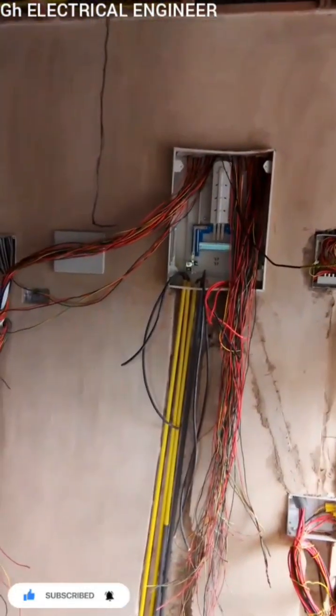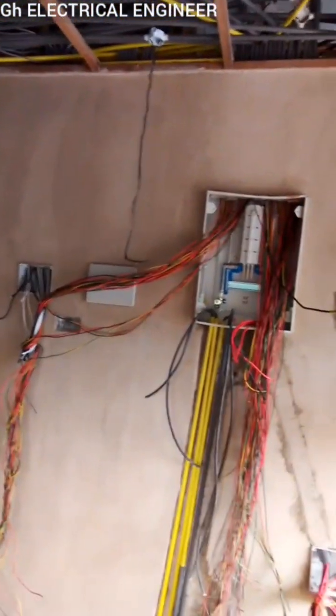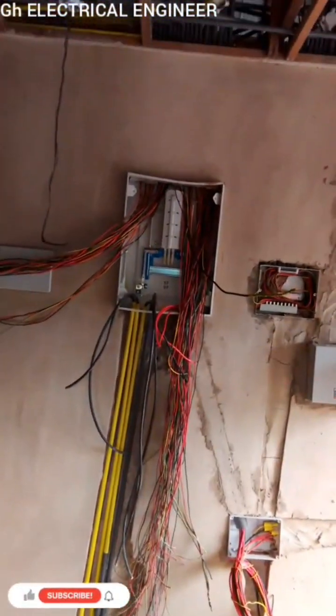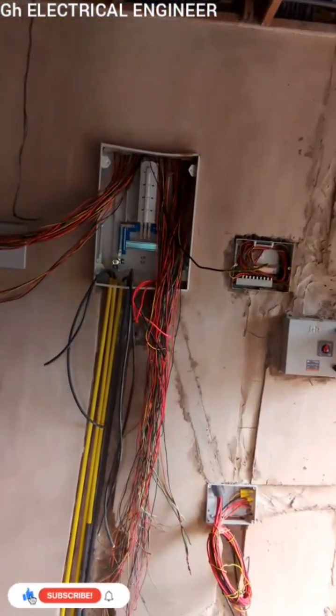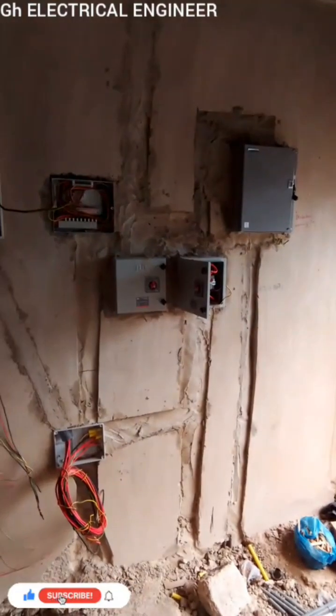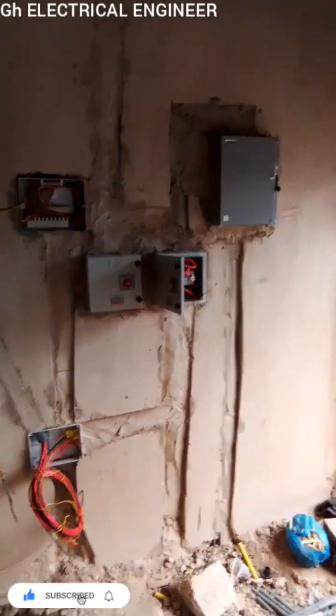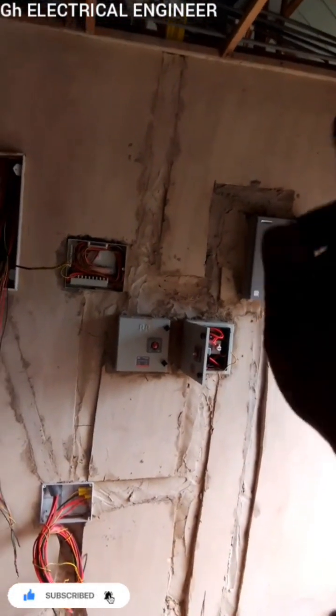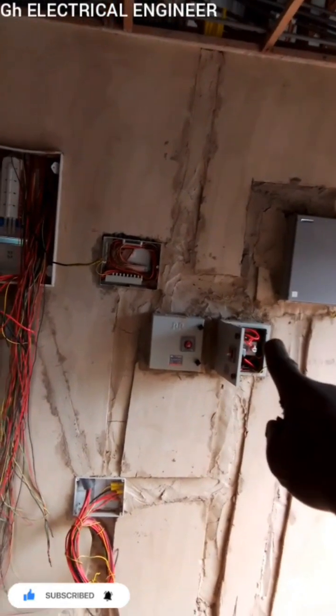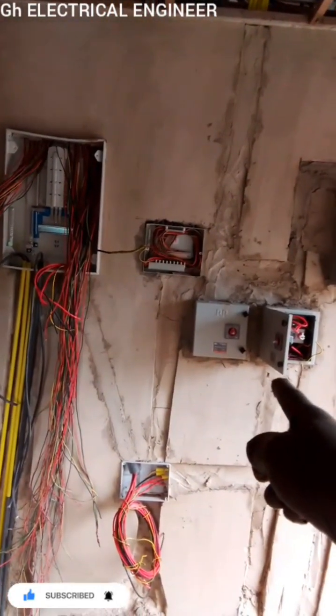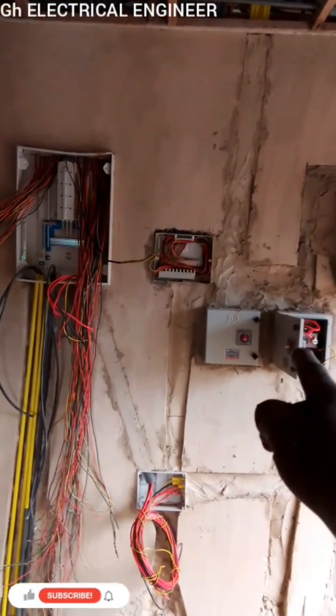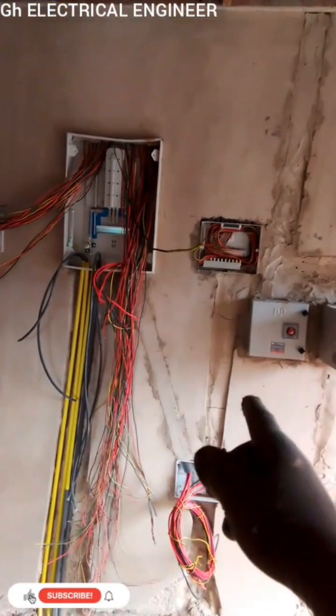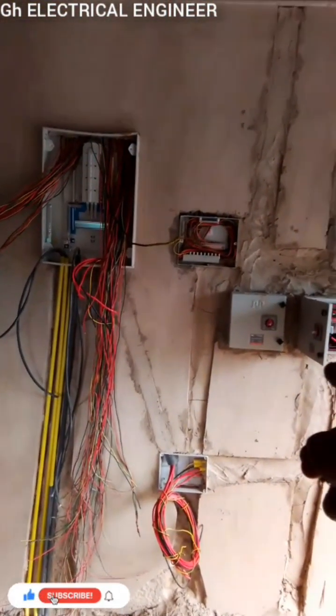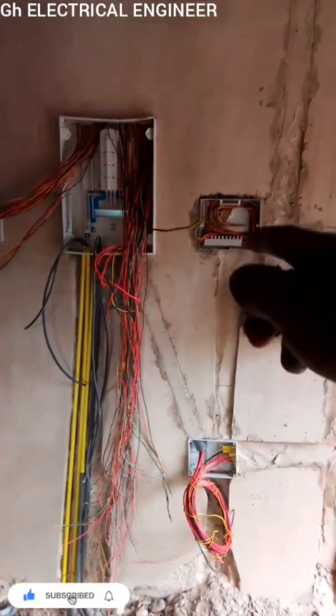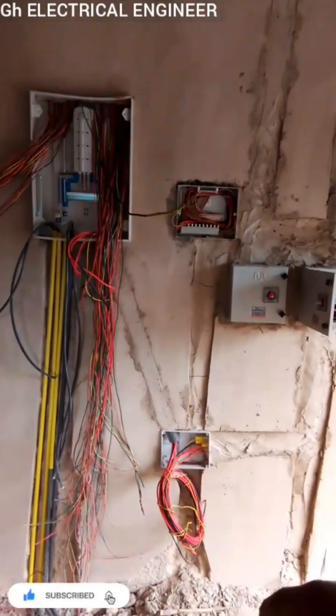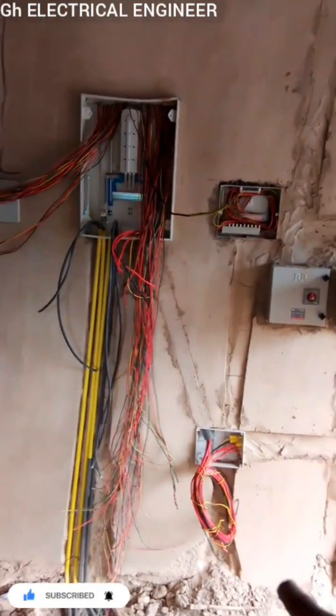From the residual current device, it transfers to the distribution board, to all the breakers in the distribution board. So it's really resilient, but it's really simple. Power comes from the ACG to the main incomer. From the main incomer, it comes to the manual changeover. From the manual changeover, it goes to another changeover, which is the solar changeover. From the solar changeover, it comes all the way down to serve the AVR, which is the automatic voltage regulator.